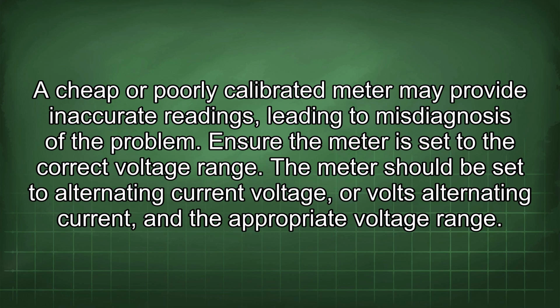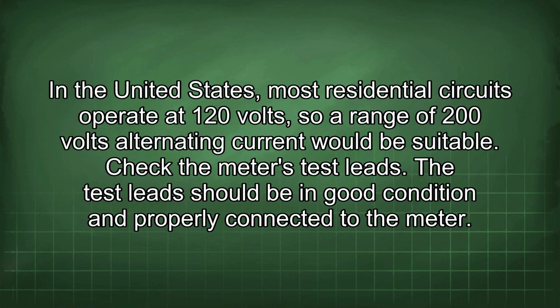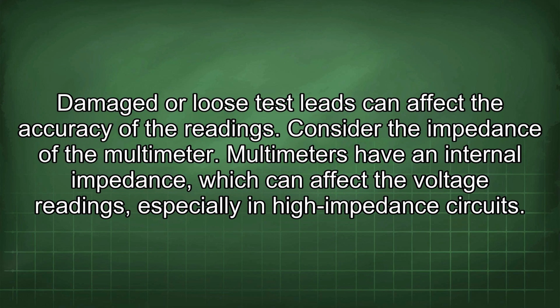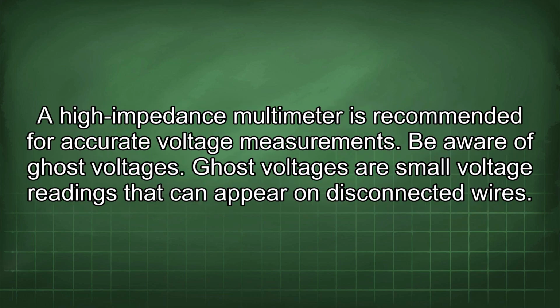Ensure the meter is set to the correct voltage range. The meter should be set to alternating current voltage, or volts alternating current, and the appropriate voltage range. In the United States, most residential circuits operate at 120 volts, so a range of 200 volts alternating current would be suitable. Check the meter's test leads. The test leads should be in good condition and properly connected to the meter. Damaged or loose test leads can affect the accuracy of the readings. Consider the impedance of the multimeter. Multimeters have an internal impedance, which can affect the voltage readings, especially in high impedance circuits. A high impedance multimeter is recommended for accurate voltage measurements.